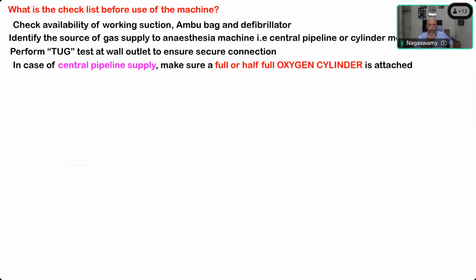You do not know when the central supply may fail. So the most important safety feature is that, even if nitrous oxide is not there and air is not there, at least one full or half full oxygen cylinder should always be attached, and should be opened and verified before you start the anesthesia in the patient. Then you can close the cylinder, but you must open it. The key to open the cylinder should be available in the machine, and if you do not check at the time of emergency, you cannot be running about for the key to open the cylinder.